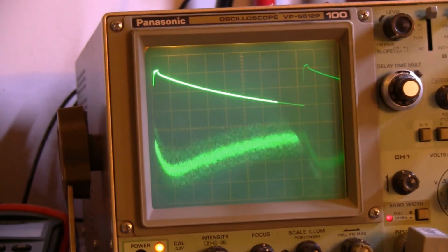The amount of current in the wire is very low, running about plus and minus 40 or 50 milliamps right now, and the probe I've got was really designed to look at signals in the amps. I bought the wrong probe, so it's noisy. Ignore the noise on that bottom trace, and you can see that we are running a reasonably straight-ish kind of ramp signal.